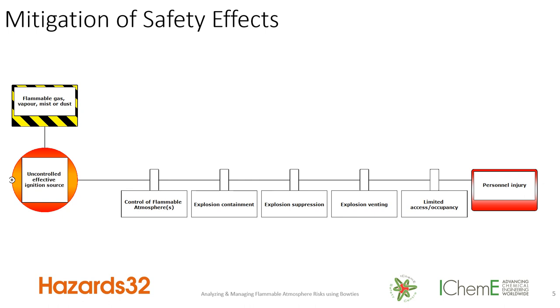To mitigate the effects on people, we would control the flammable atmosphere and try to eliminate or reduce its likelihood. We would aim to contain the explosion, or if it can't be contained, to suppress it so the overpressure doesn't increase — or discharge that overpressure to a safe location. To protect people, if we exclude or limit the time they are present, there is less likelihood of actually injuring somebody.